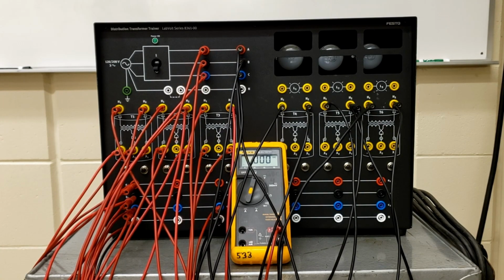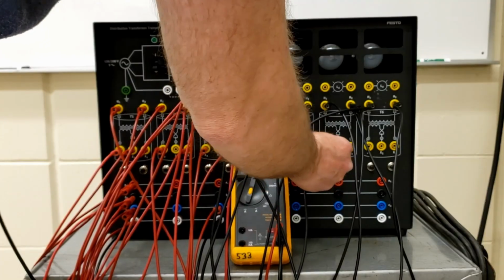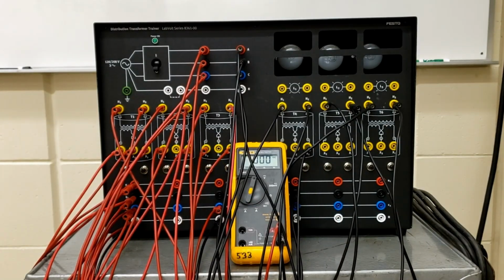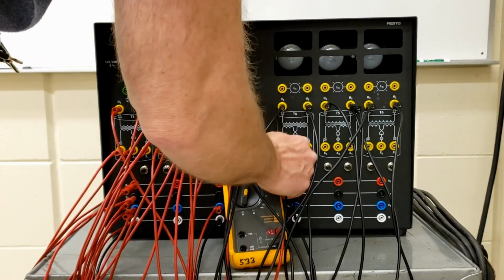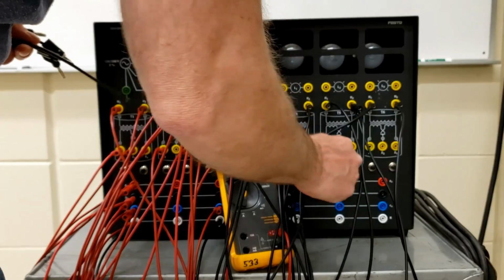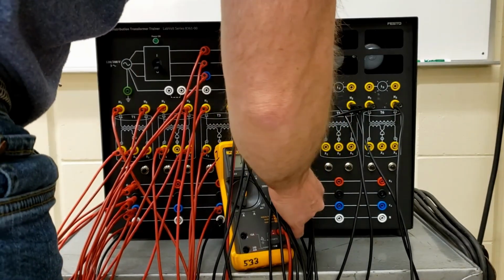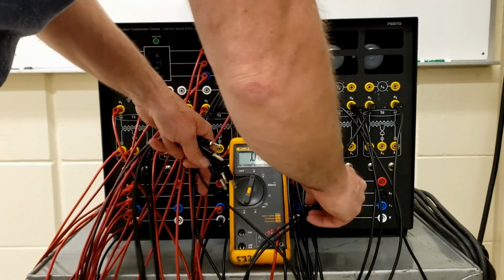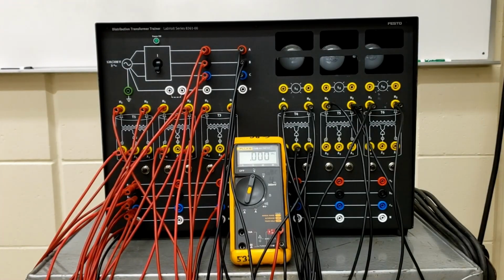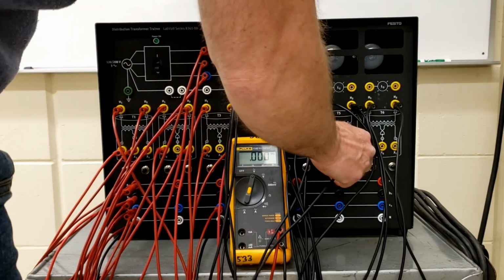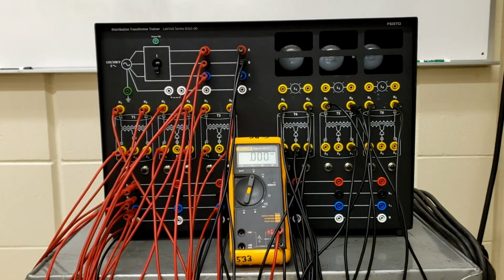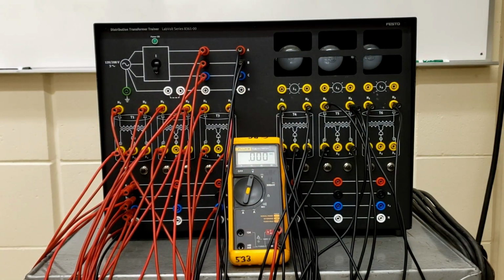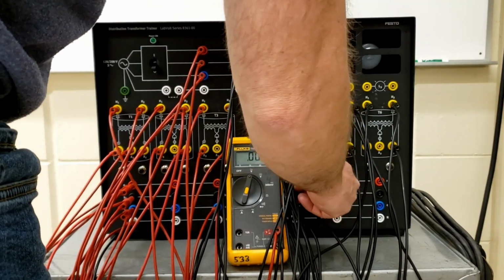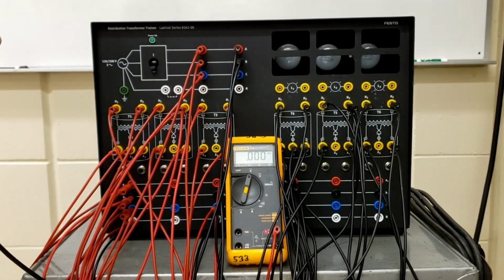Secondary is going to be X1 to B. This is 180 degrees from the other one, right? So X1 to B, X3 is going to A. And then we'll also have X2 bonded to ground on the first transformer. Let's get these guys out of the way. On our second transformer we have X1 going to C, X3 of our second transformer going to B. And on the third transformer, we have X1 going to A and X3 going to C.